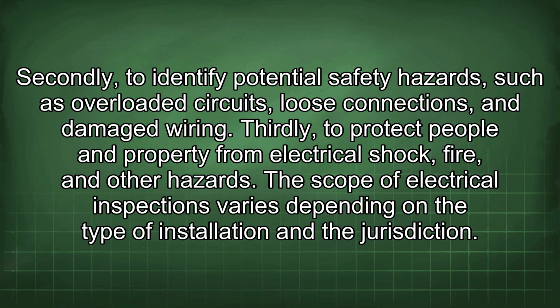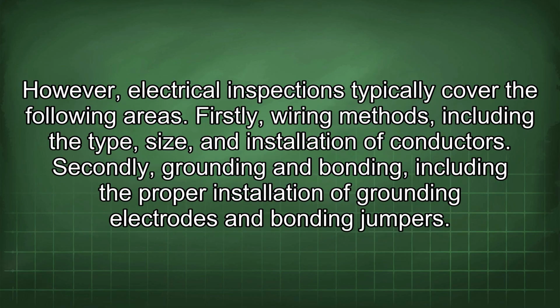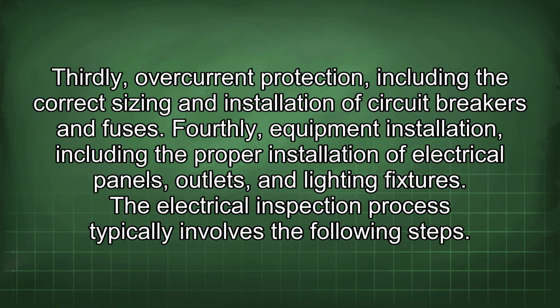The scope of electrical inspections varies depending on the type of installation and the jurisdiction. However, electrical inspections typically cover the following areas. Firstly, wiring methods, including the type, size, and installation of conductors. Secondly, grounding and bonding, including the proper installation of grounding electrodes and bonding jumpers. Thirdly, overcurrent protection, including the correct sizing and installation of circuit breakers and fuses. Fourthly, equipment installation, including the proper installation of electrical panels, outlets, and lighting fixtures.